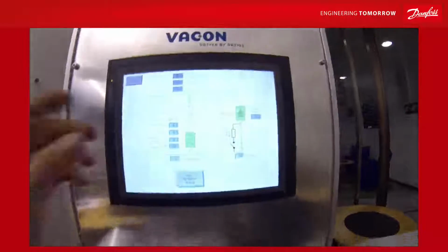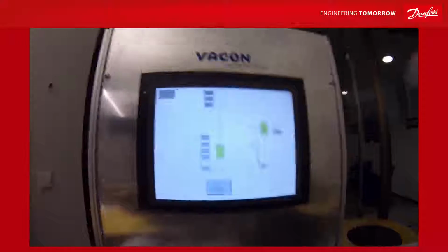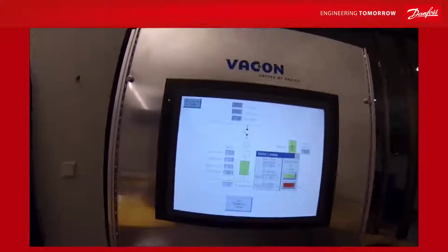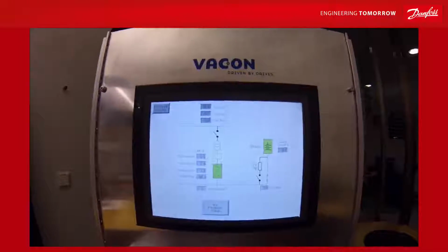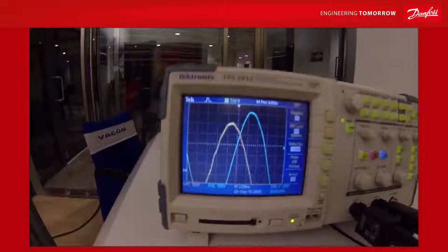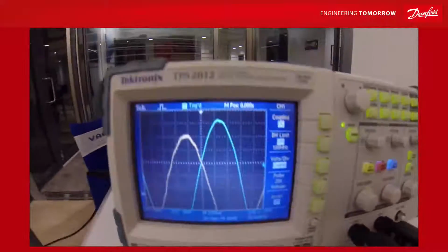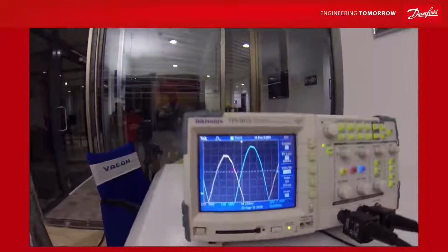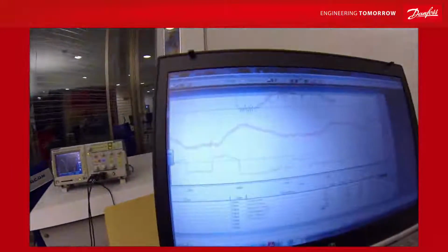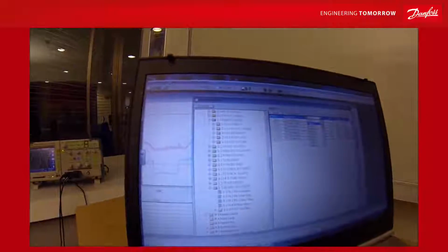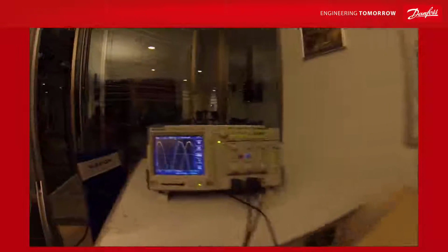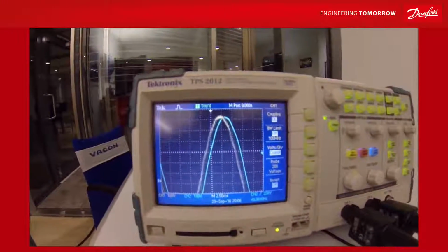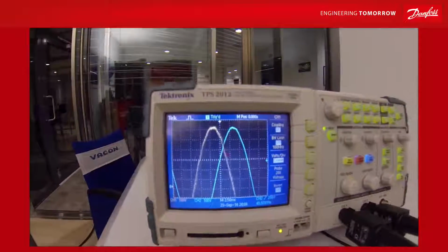So when I'm going to synchronize two networks, then it is what I'm looking for. If I'm opening this now, we are not in synchronous anymore, as we can see. We are missing the voltage, we are missing the frequency, we are missing everything. How do we get it to synchronize? First of all, using the PID regulator when we are not connected to the grid is not a good idea. So, get the PID regulator off. And now we see that the frequency is drifting.